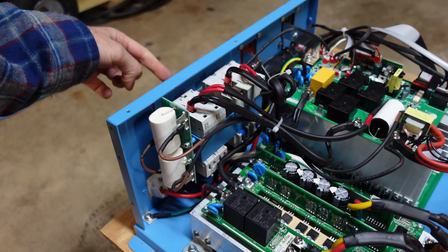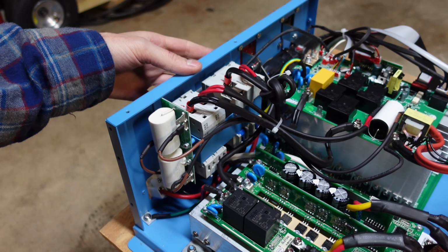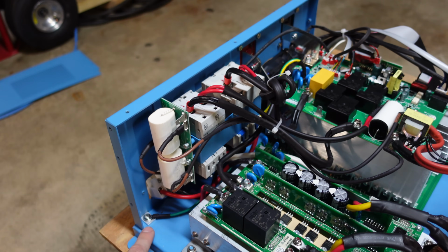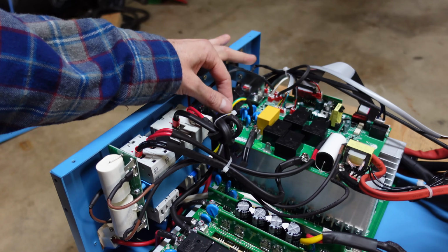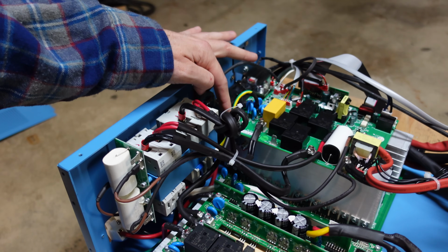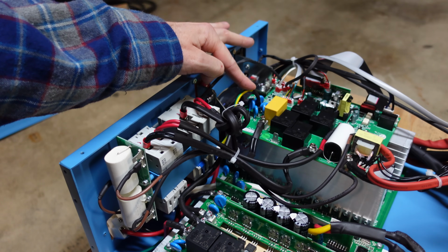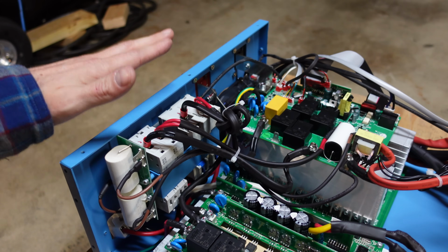The ground screw on the front of the input block is connected to 2 different locations. There's a green wire that comes down here to bond the ground to both the enclosure chassis as well as the giant ground lug on the front. Additionally, we have a thicker 12 gauge wire that comes off of the terminal block and goes up into the main circuit board here. So this entire thing operates on one ground.